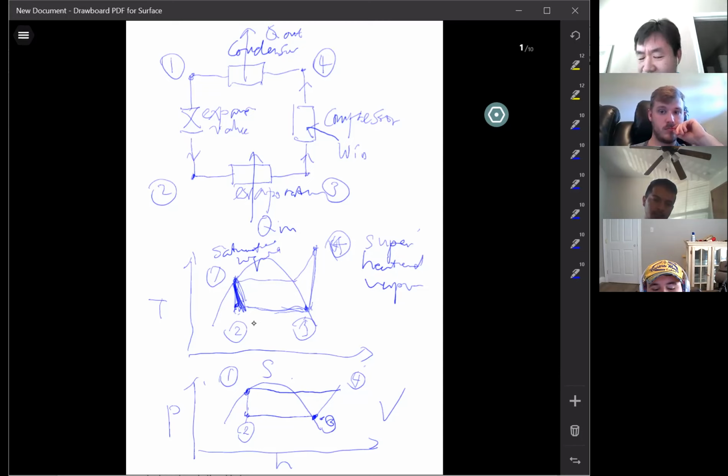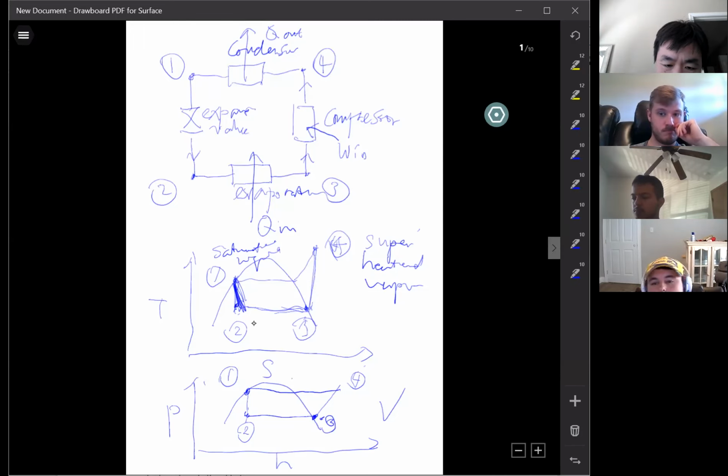So how do you find the degree of superheat? It's not called overheat, okay? It's easy. On this pH diagram, there are temperature lines, so this point indicates a temperature. There's a temperature line across this point, so you know the actual temperature here, which you just measured.